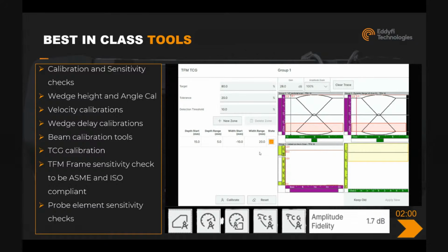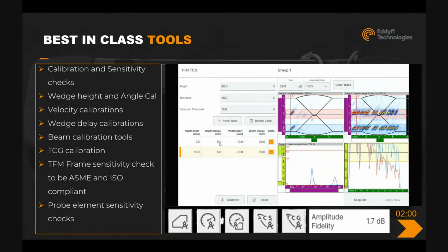Also quite nice is the TCG setup. In this case, you see a little red bar here, and I'm going to add a zone. The zone is actually for this calibration block here. And what I can now do is quite easily add my calibration in my zone, and I can add a new zone as well. So this new zone is going to be at 16. So two zones created, and I'm currently looking here at my response. I want to make sure that my response is not exceeding 80%, which it is, so I'm going to bring the gain back a little bit to make sure that I'm not saturated.